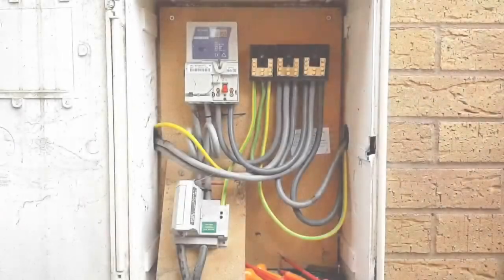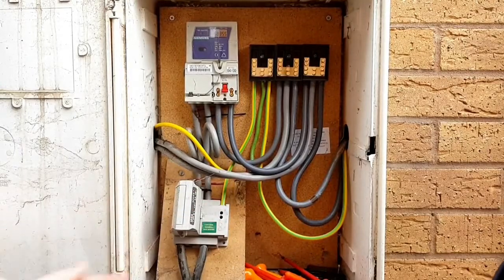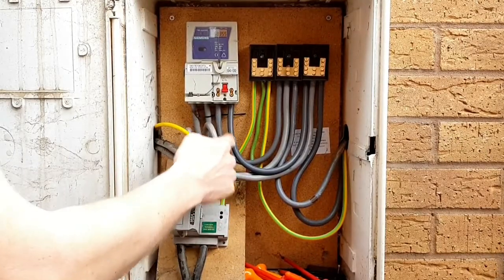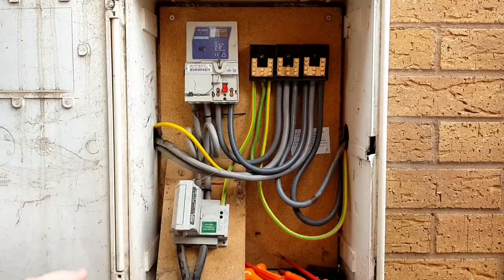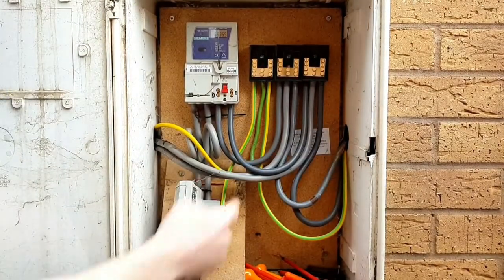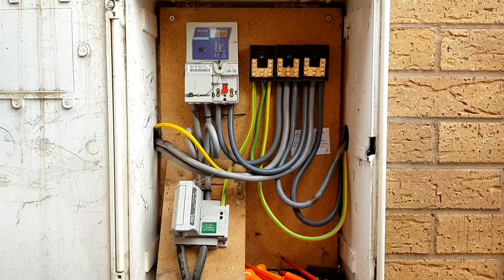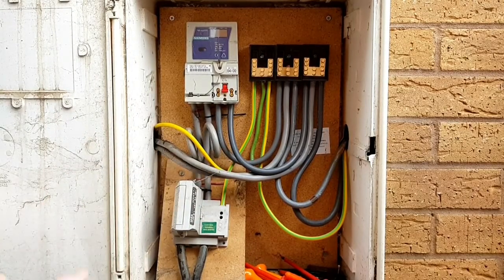Connection. Okay, Gary, so we have now split the tails successfully. We've got our new supply going out to the Henley blocks. We've got our new tails going out to the new consumer unit, existing tails going out to the existing consumer unit, and that's really good because we're now in a position where we can think about fitting the clamp meter in the correct position.